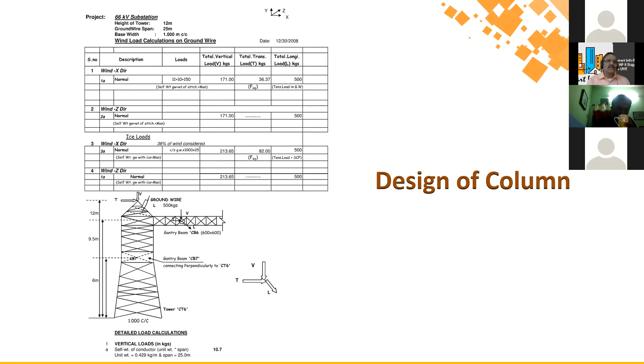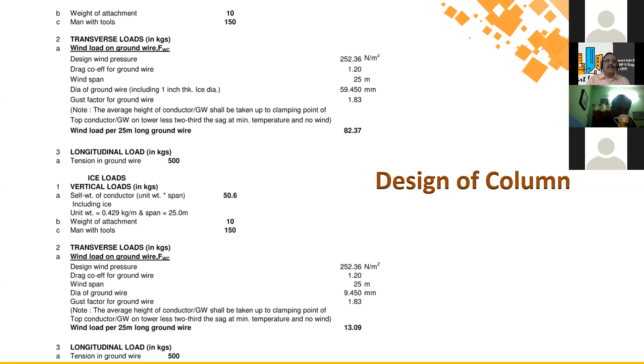depending on the earthquake. And ice loads, you can see here, we consider the ice on the conductor also. Because wherever it is, if it is in the northeast or north, wherever the low temperatures are there, the ice load is considered based on the thickness of the ice. That is a design parameter. And weight of attachments, man with tools during maintenance, all these loads are considered. So here you can see I have shown this beam in all three directions. This is the longitudinal, this is the transverse and vertical load. So these are the three loads, and you can see there are three conductor points on this beam.